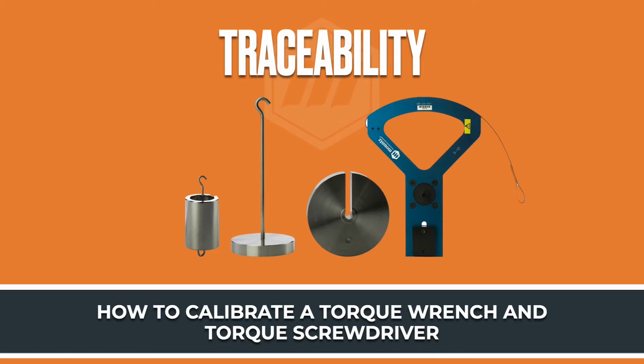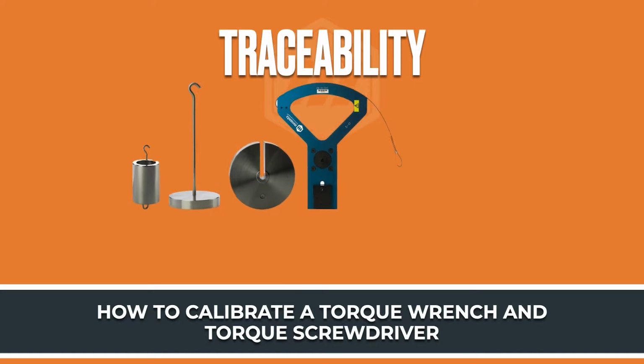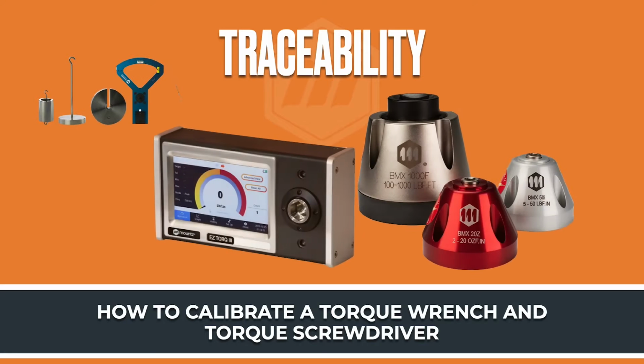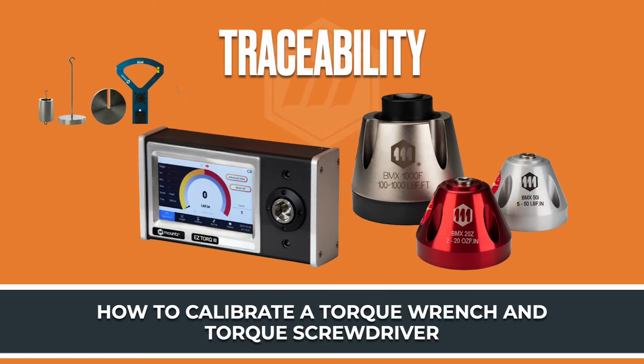We use a dead weight system, which is using our length times our force. And this is the unit that we use, or the types of products that we use to calibrate a torque analyzer. So that system is traceable to the weights, or to the scales that may be used to measure those wheels and weights. Those are what we use to calibrate the torque analyzer.